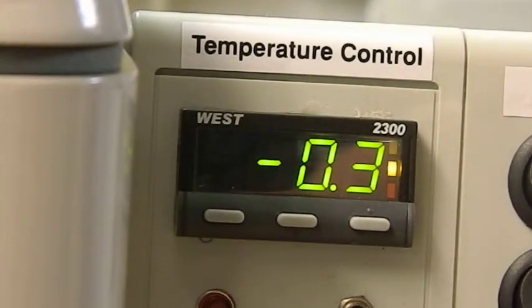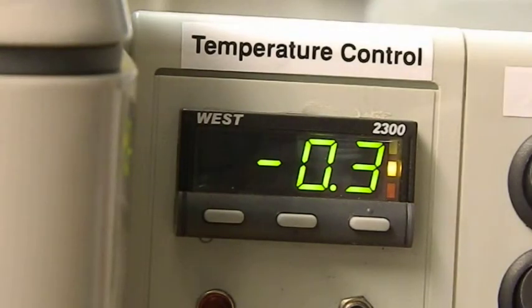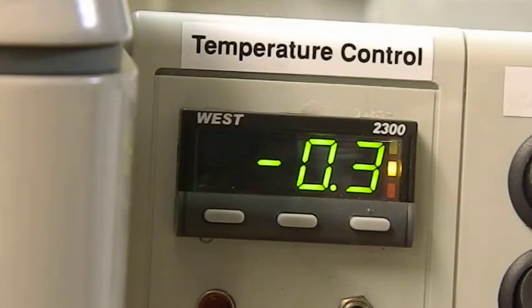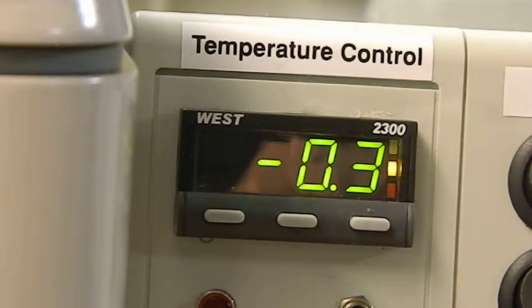Okay, so we check that again, quick another look at the thermometer. Yeah, it's still at 16.1 and the controller was at 16.4, so it's 0.3 difference. The controller is high compared to the actual reading in the machine, so you put in a minus figure. If it was the other way around and the controller was below the actual temperature in the machine, you put in a positive figure. Okay, we'll just wait for this to time out now.